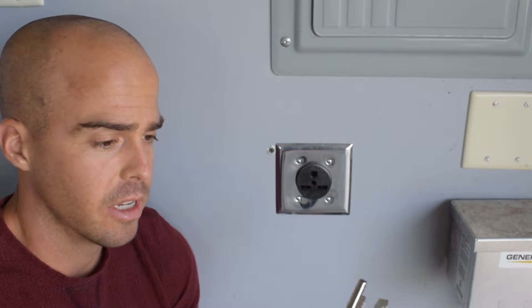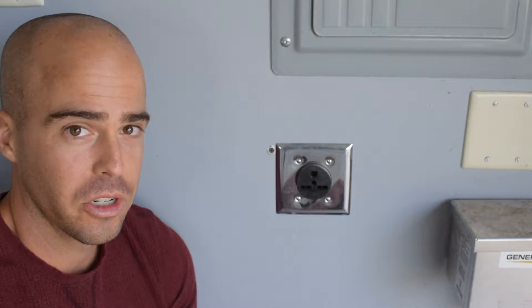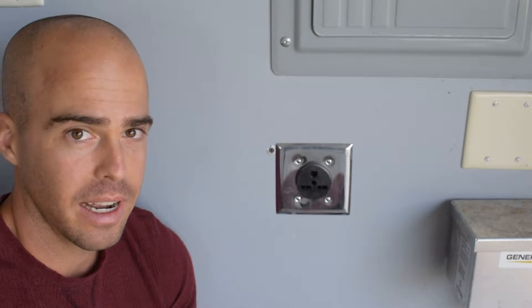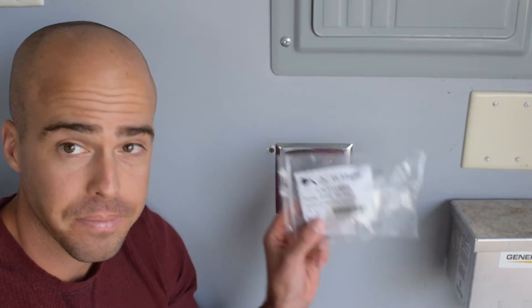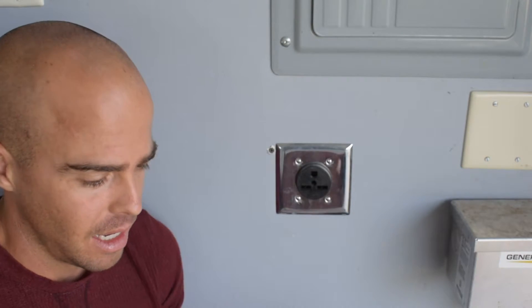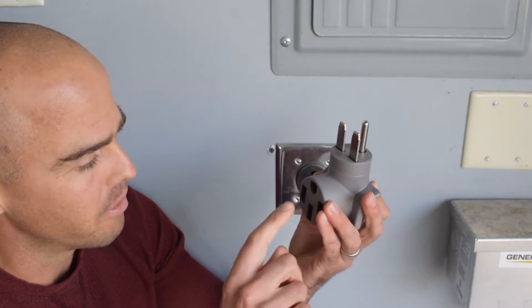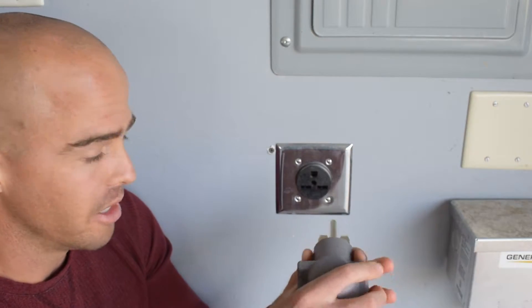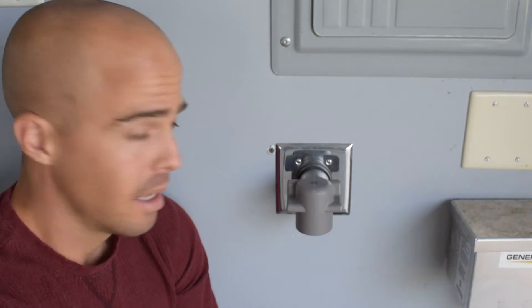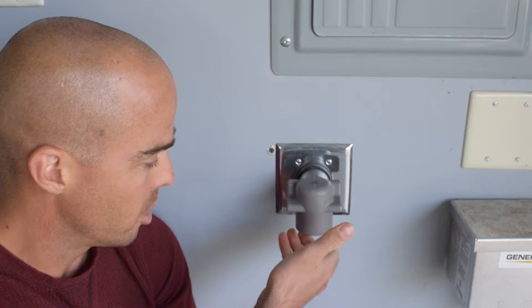First things first — because this outlet is a NEMA 6-30R, and most level 2 EV chargers have a NEMA 14-50 plug, the first thing I had to do was get an adapter. So I did some searching online and from AC Works I bought this handy, nifty 6-30P to NEMA 14-50 outlet right there. So what that's going to do is simply plug in like that, nice and solid, and then the level 2 charger is going to plug in right there.